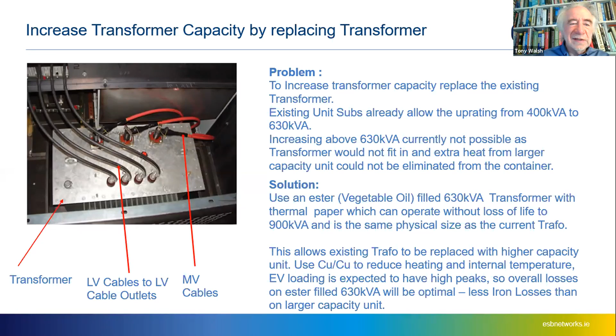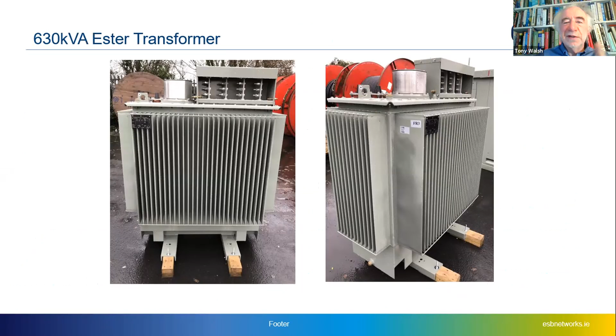We used a vegetable oil, which can operate at a higher temperature, so we have a higher power density, and operating at a higher temperature in such substations doesn't cause the paper insulation to deteriorate. So that 630 kVA transformer can be replaced with one that's also nominally 630, but can be overloaded at peak to 900 kVA for many hours at a time. So it's a very economic solution. And the cost of this is not much more than the cost of the transformer itself. It's maybe another 15, 20%. That's one that we've manufactured in Cavan, and we've got tested and it works.